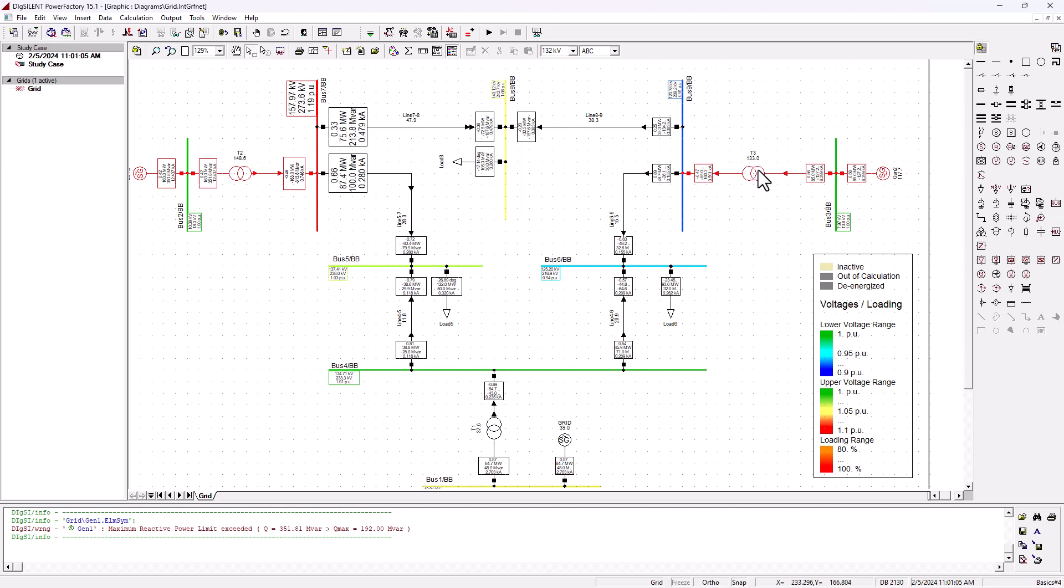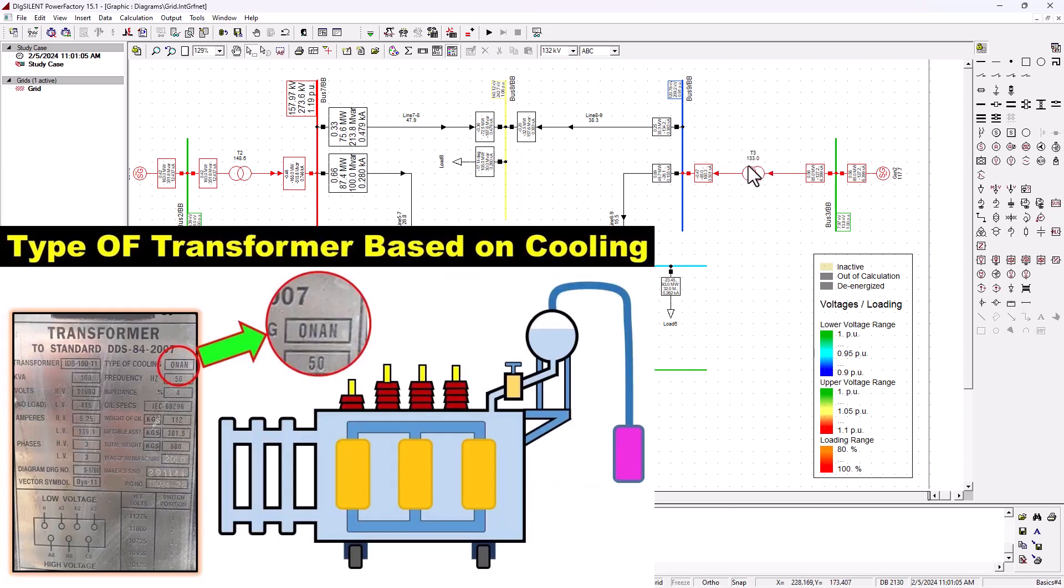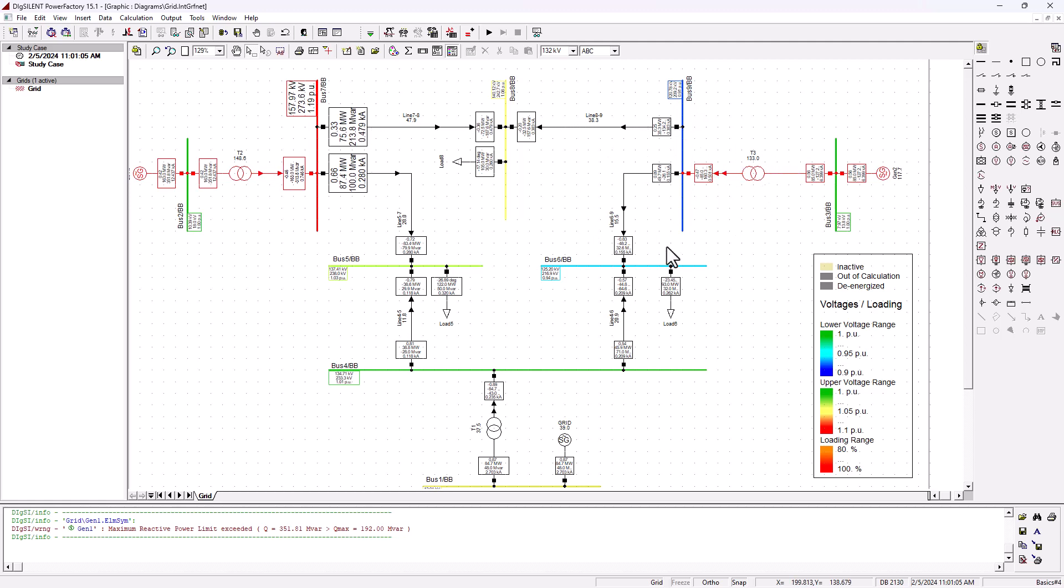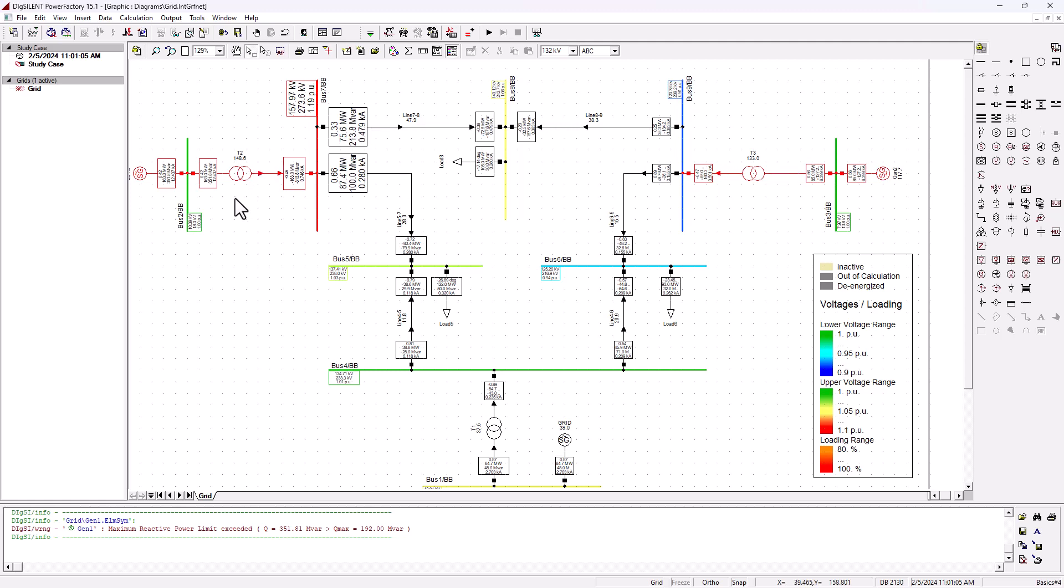We can still accept seventy five or even 80 percent, but as soon as we start to go above 80, we're approaching the red zone. Hundred percent loading means basically there is no room for the transformer to breathe. Depending on the type of cooling of this transformer, whether it's forced air cool or ventilation, this transformer will be working overtime and it's only a matter of time before it actually explodes.